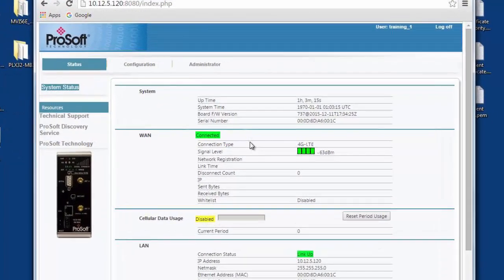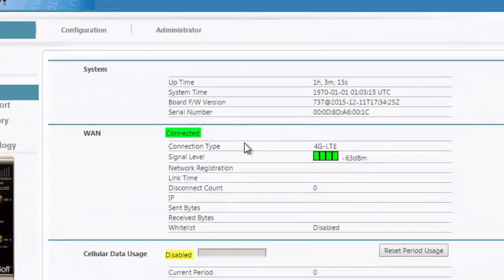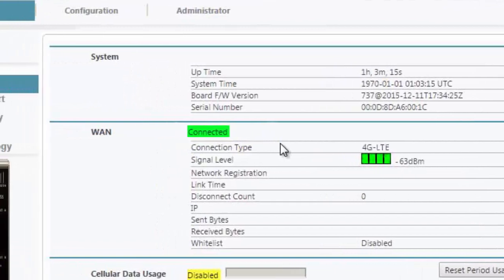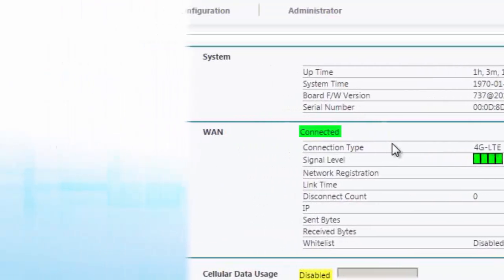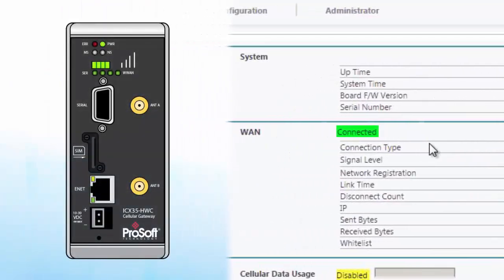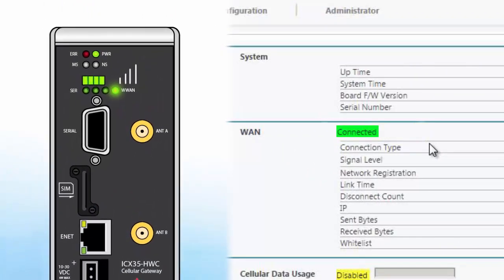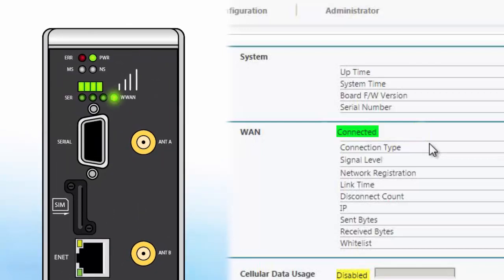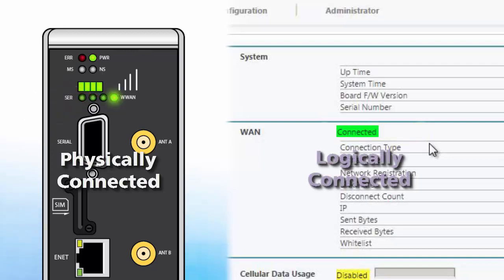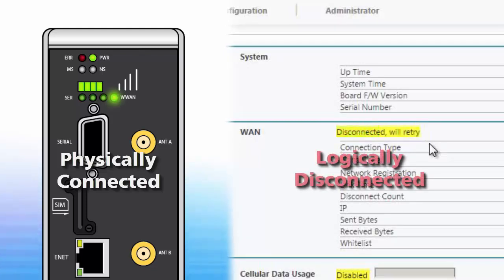One last thing to note. There are conditions where the connection status indicator in the ICX-35's configuration page may seem to contradict the status that is indicated by the WWAN LED on the front of the modem. This is because the LED on the ICX-35 shows the physical connection status of the modem to a cell tower, whereas the status indicator in the user interface shows the state of the logical connection, meaning the modem has negotiated with the tower and obtained an IP address. The modem could potentially succeed in connecting physically to a cell tower but then fail to obtain an IP address. In this instance the LED on the front of the ICX-35 would show a connection while the user interface would show no connection.